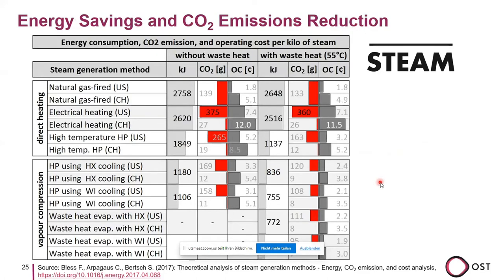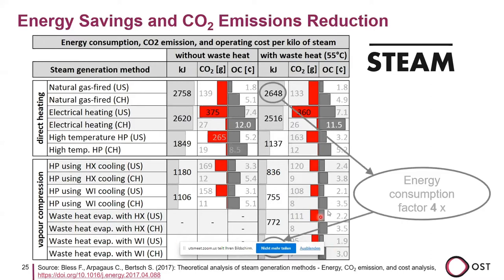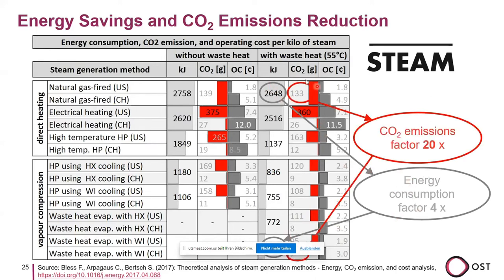And when we look at the energy savings, the CO2 emissions reduction, and the operating costs, we can compare these kinds of cycles or systems. For example, here is a natural gas-fired boiler for the US or Switzerland, and here at the bottom is the system shown with vapor recompression. You can see that the energy consumption is reduced by a factor of 4 and the CO2 emissions by a factor of 20. So quite substantial factors.